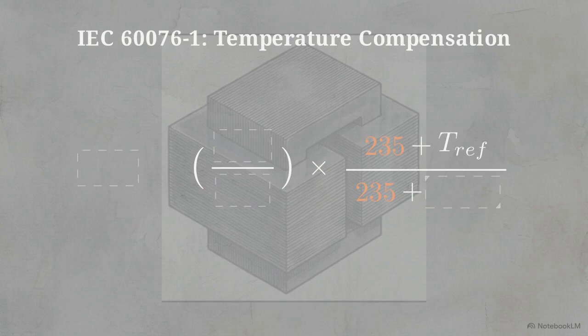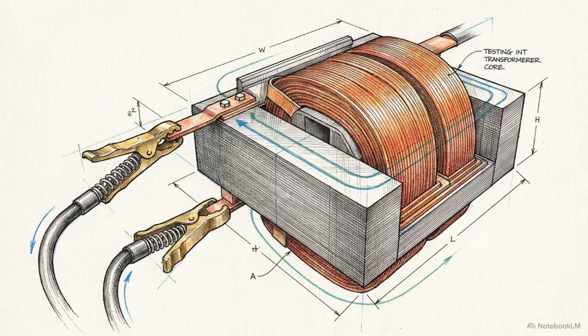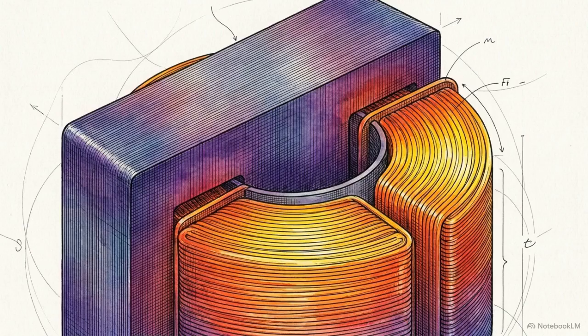The system utilizes a formula defined by IEC 60076-1 to mathematically normalize the raw resistance reading. It takes the measured voltage, current, and ambient temperature and outputs a calculated resistance against standard reference temperatures. Because the internal coil of a VT is highly inductive, it resists the sudden flow of direct current. The injection takes significant time to saturate the core and stabilize before a valid reading can be captured. Capturing this precise measurement establishes a thermal baseline. It proves the physical copper path is intact and won't experience thermal runaway when exposed to continuous grid operations.